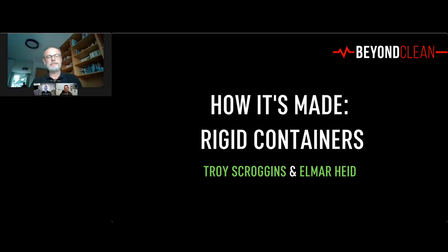Right. Well, the stackability of containers is a basic requirement of our ISO and European standards for rigid sterile containers. So every container of the same type must be stackable during sterilization. Same type means manufacturers do not need to meet this requirement across brands, but of the same type and family, the same brand, they must. That means there's always enough space, even if you stack containers, to remove air and to allow steam to penetrate during sterilization.